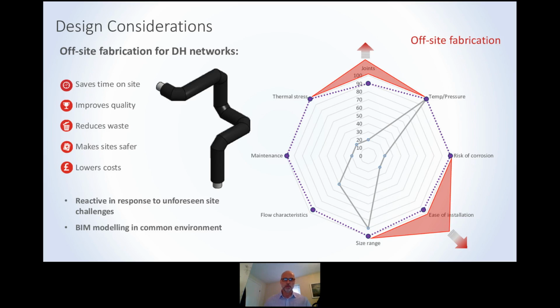Then just to close up this spider graph, there's the areas of ease of installation and jointing. To reduce the amount of joints and ease installation, we have an off-site fabrication facility which is being used more and more for heat networks. Typically it saves time on site, improves the quality, and everything's tested in our works and certified before it goes out. We can do this with steel, copper, plastics.